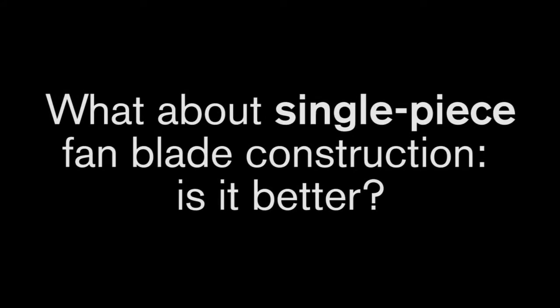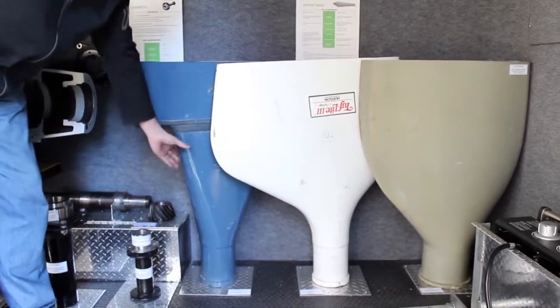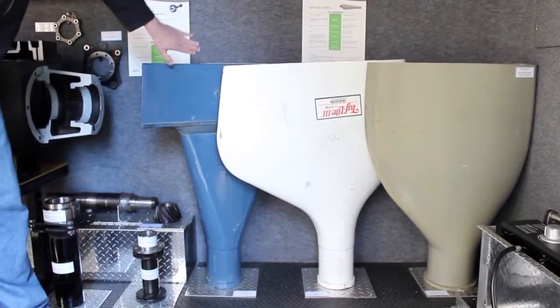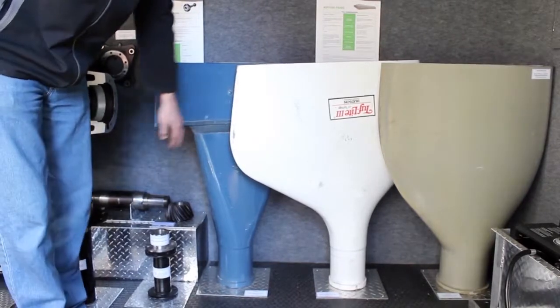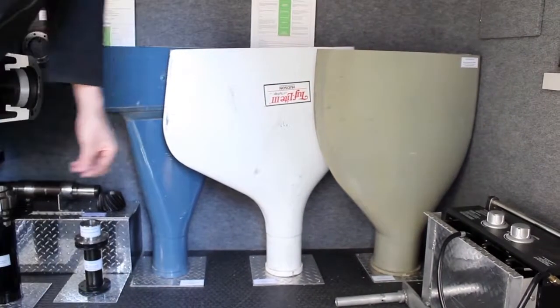What about single-piece fan blade construction — is it better? The Hudson Tuf-Lite II blades, which are very common in the field, are actually two pieces. They have the main shank portion and then a rubber boot with a mechanical joint going to the rest of the blade. Obviously you have some stress concentrations that can build up there, which is a concern. Hudson has changed that with Tuf-Lite III — they've gone to more of a single piece, like the Marley has been for many years.